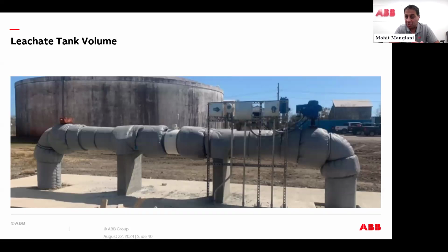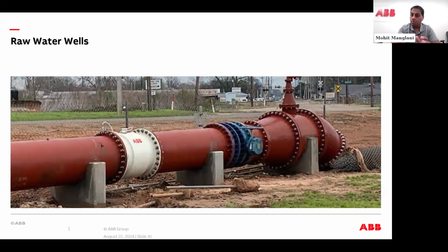Leachate tanks, not the prettiest application, not the best smelling application, but a great application for a mag meter. Teflon liner, typically Hastelloy C or platinum electrodes to hold up against the process itself. Raw water wells for source water. If you're pumping water out of the ground with a nice pump, obviously you want to validate and check that pump. You have your pressure gauge on your pump to validate the flow curve is operating efficiently. The mag meter is a tool to verify that pump.